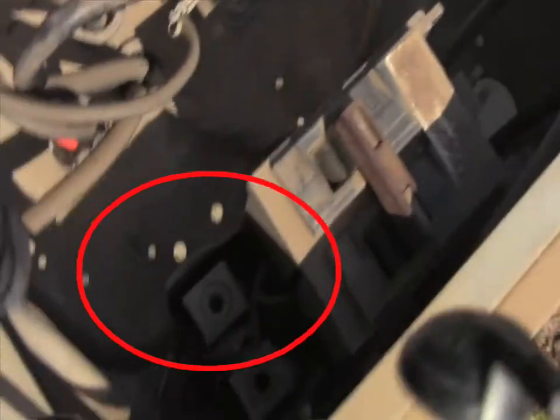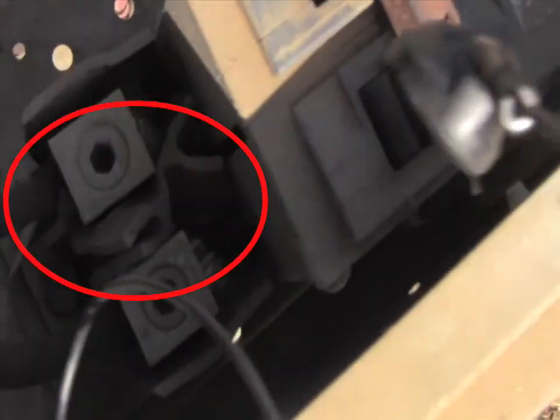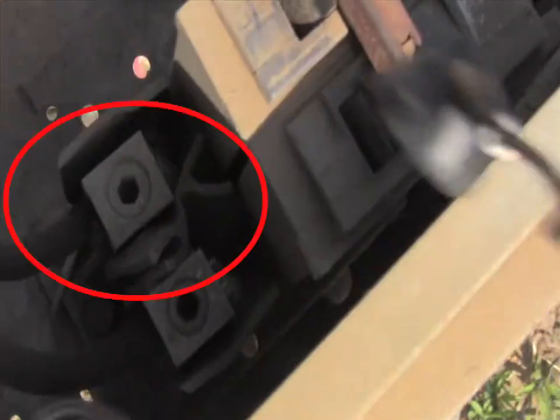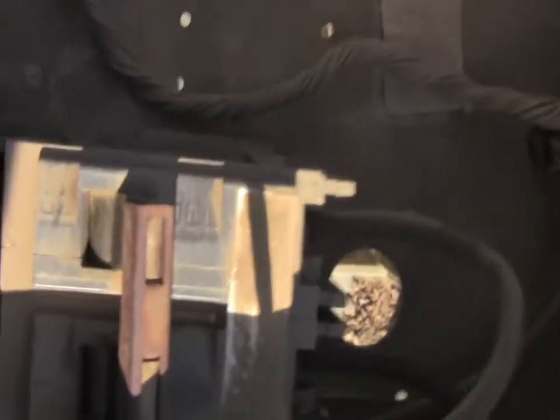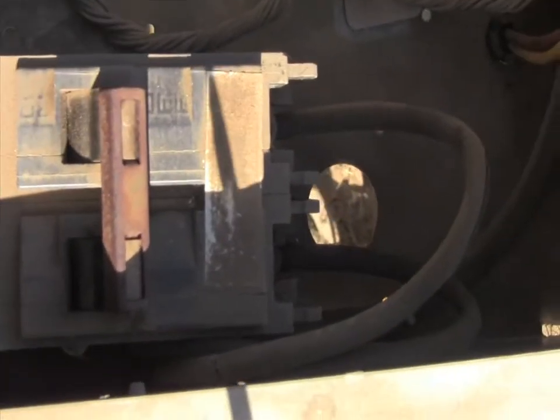We're going to look inside the box right here, and this is the master on-off, which I've switched off right now. And this is full of live electricity, so don't just arbitrarily go touching stuff. Those contacts will stay energized unless you turn off the main circuit breaker to the air conditioning unit at the circuit panel. So there's your safety on-off right here. This is your main on-off right here inside the unit.